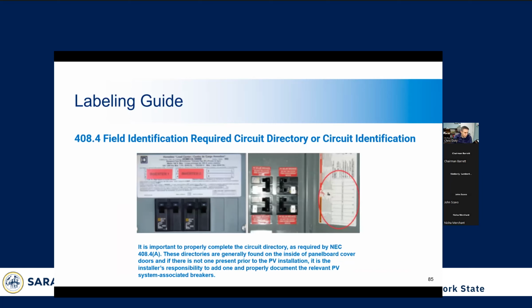Here we have a situation where the installer didn't label the sub panel, so who knows which breaker goes to what. That is potentially a problem down the road if someone has to shut the system down. But having this properly labeled is part of the general electrical code, not just the PV code, and so that still has to be followed.